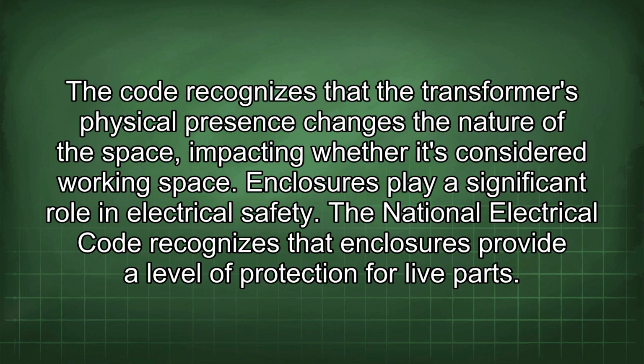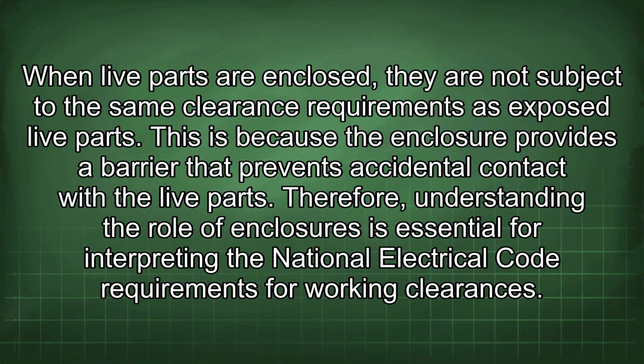Enclosures play a significant role in electrical safety. The National Electrical Code recognizes that enclosures provide a level of protection for live parts. When live parts are enclosed, they are not subject to the same clearance requirements as exposed live parts. This is because the enclosure provides a barrier that prevents accidental contact with the live parts. Therefore, understanding the role of enclosures is essential for interpreting the National Electrical Code requirements for working clearances.